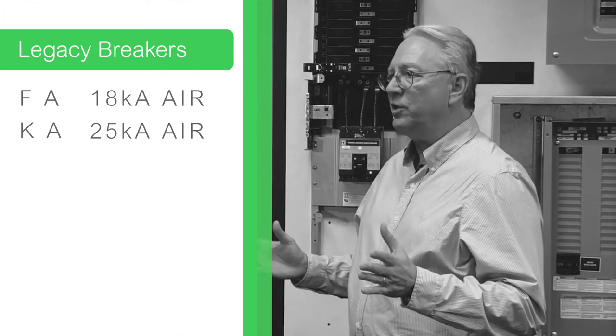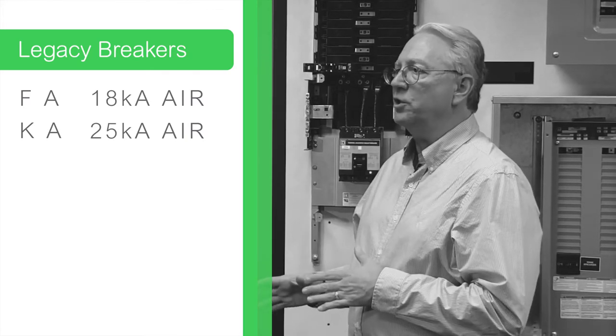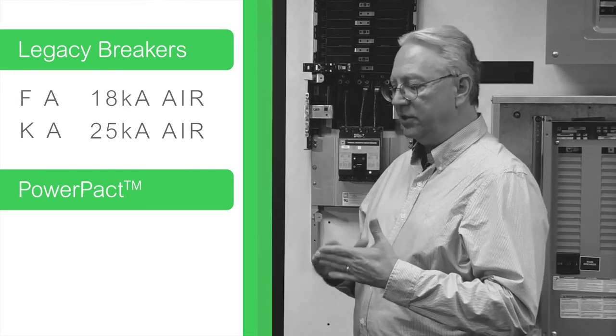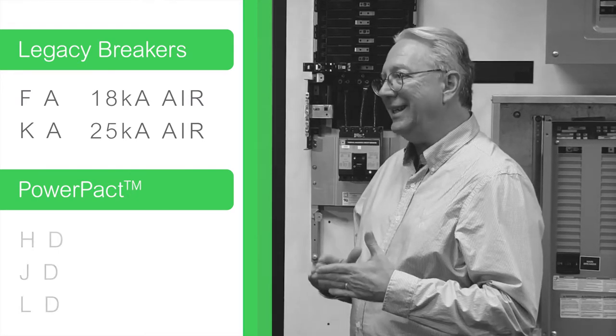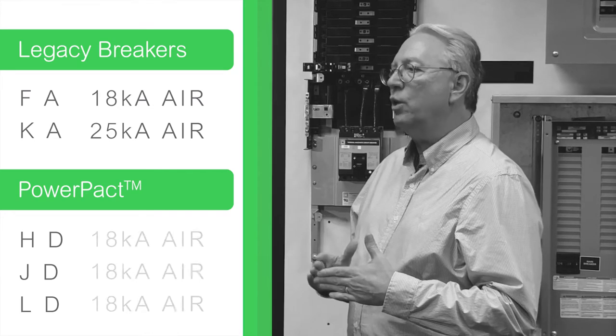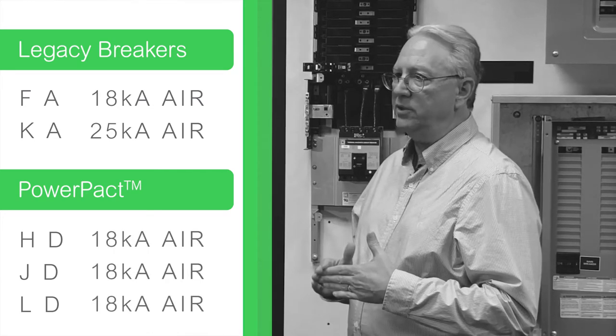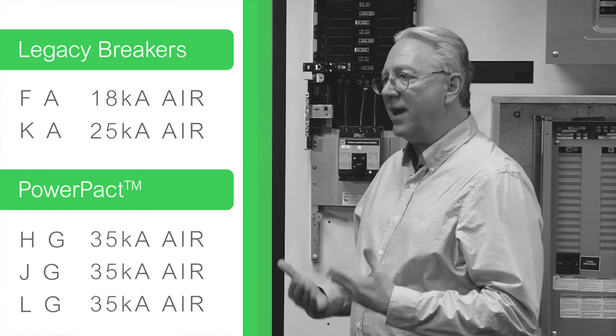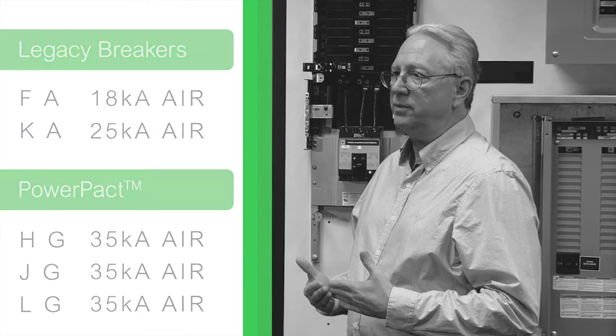We've taken that mystery out with the PowerPact breakers. Now if the second character is D, it can withstand 18,000 amps regardless of what the frame size is. If the second character is G, it can withstand 35,000 amps regardless of what the frame size is.